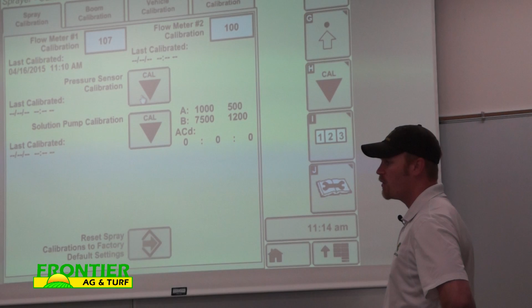Like I said, do this one for sure every spring before you get going. If you change anything in the system hydraulically, you've got to recalibrate. So if you replace the PWM, the compensator, control valve within the hydraulic system, part of that solution system, do the calibration again because things have changed. Okay? Change out a solution pump, do the calibration. You went from an old one to a new one, so there's some differences there in the resistance of the impeller and all that. Okay?